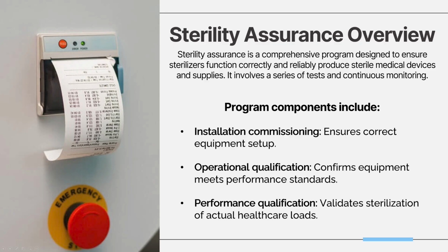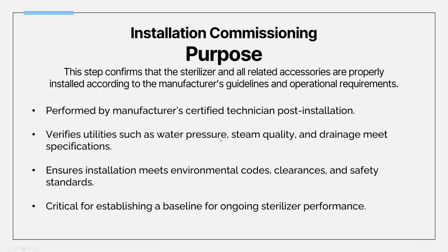Does this thing do what it's supposed to do, exactly as intended or required? And we also have performance qualification. So can it sterilize actual loads? These checks are mandated by standards, so that's CSA Z314, to maintain consistency, safety, and accountability in healthcare settings.